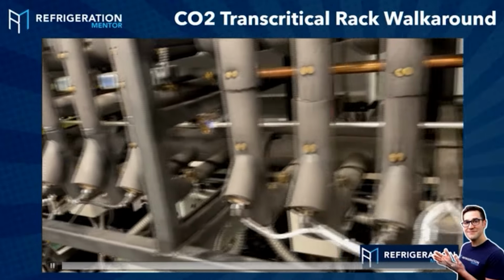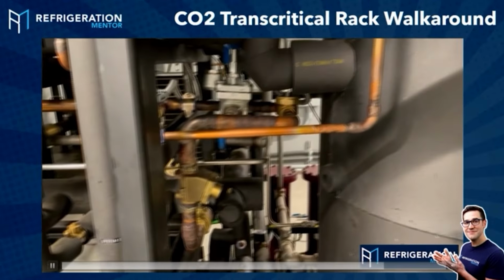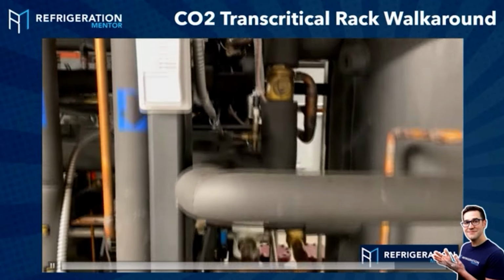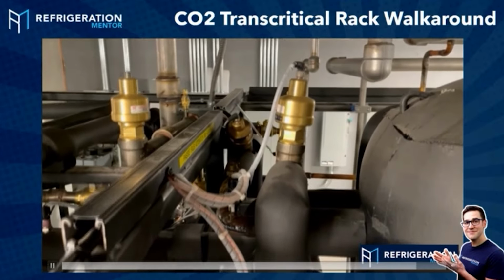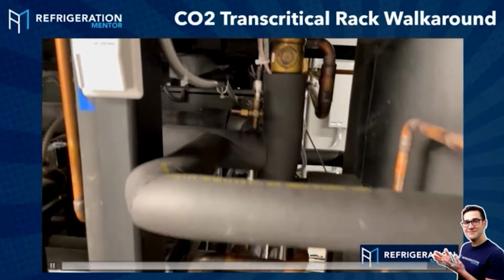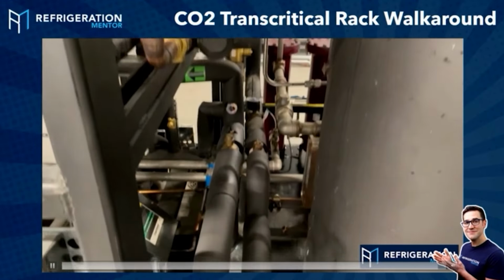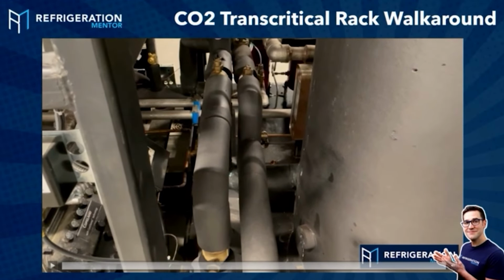Then here's some more electronic valves on the system through your suction. This is the thing that you want to relate all this stuff that you learn, all these new technologies. It doesn't matter if it's VRF or the heat pump. These are those high pressure valves I talked about. Those are the high pressure valves taking that 1500, 1400 psi, dropping it down into that liquid pressure that we're looking for, good quality liquid pressure.